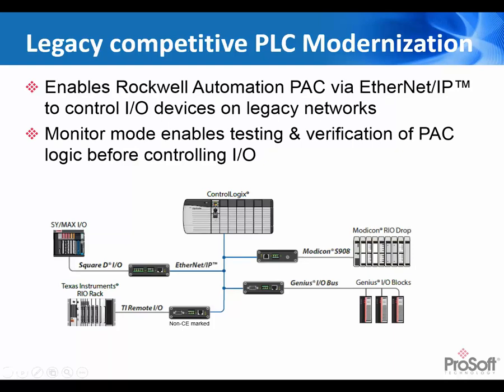With these migration gateways, they enable Rockwell Automation controllers via EtherNet/IP to control legacy networks. You're able to monitor the network before you make any changes, so you can verify your code on your logics before controlling the existing Modicon I/O or existing Genius Bus I/O.